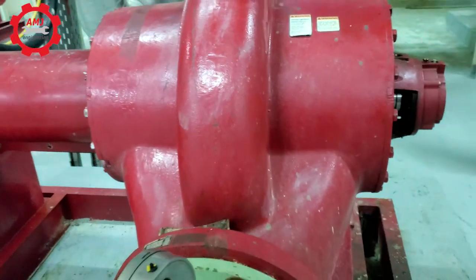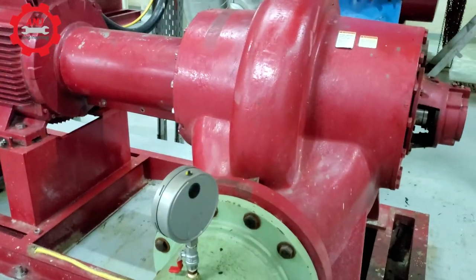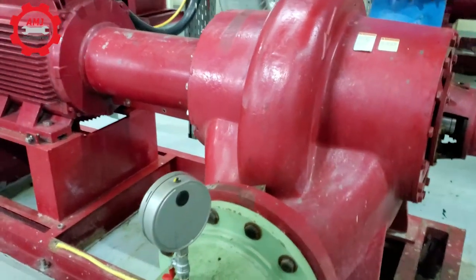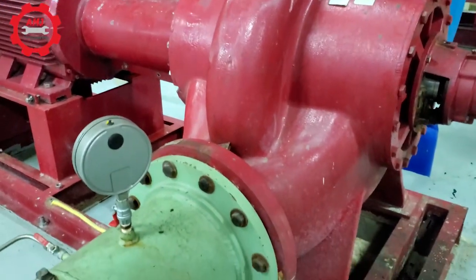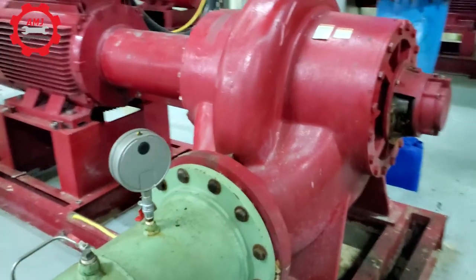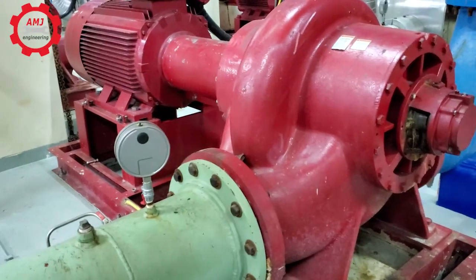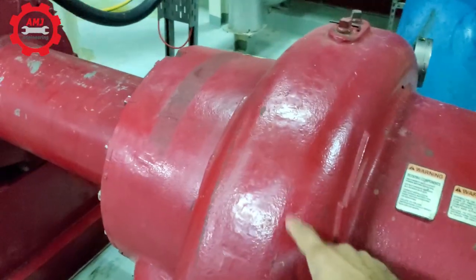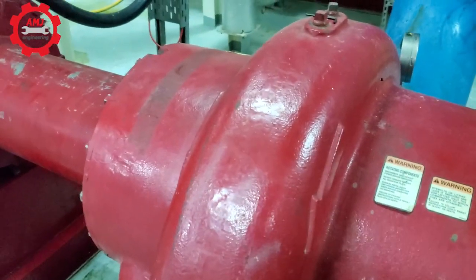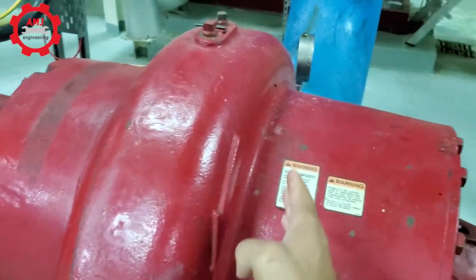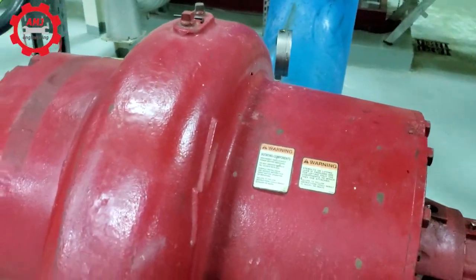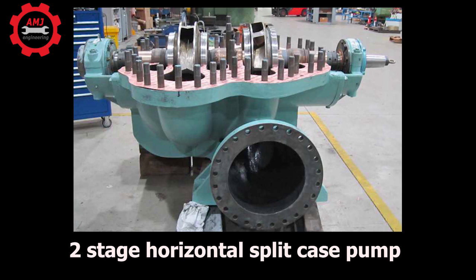Using double suction reduces the risk of hydraulic imbalance. The reduction of hydraulic imbalance is one of the reasons why double suction split case pumps are preferred over single suction. Split case pumps may have one impeller for single stage operation or may have multiple impellers for multi-stage operation. Multiple impellers provide increased available head within a single pump.